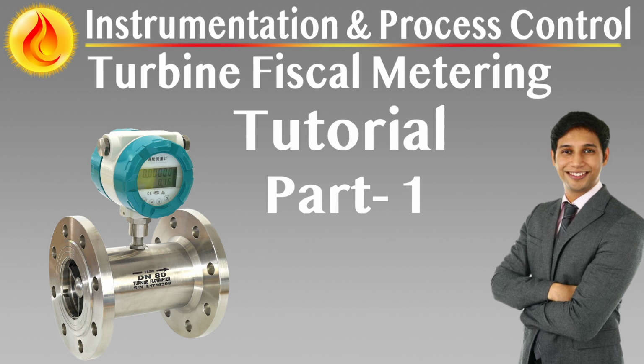4-way valve and diverter logic. For bidirectional provers, a 4-way flow diverter valve must meet API Chapter 4 specifications and be integrated into the prover automation sequence. The valve must operate without introducing shock, dead zones, or hydraulic discontinuities. Its actuation must be monitored and seal integrity verified during each proving cycle to ensure no bypass leakage. If valve performance is compromised, the proving sequence must be aborted and flagged for operator intervention.